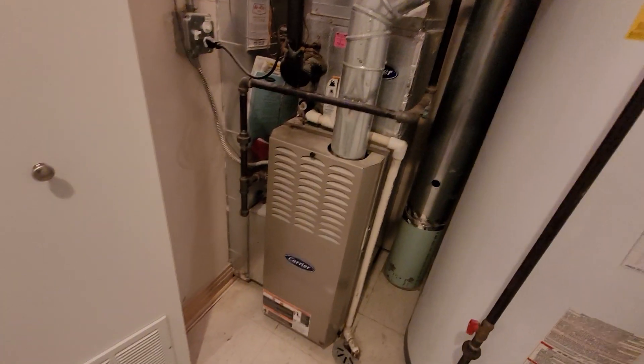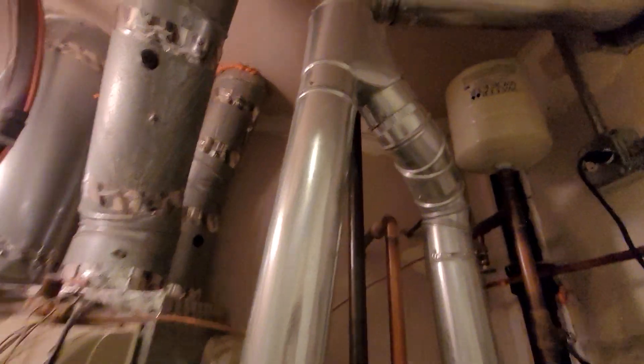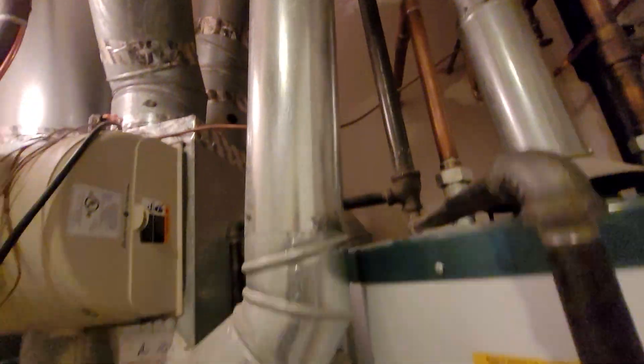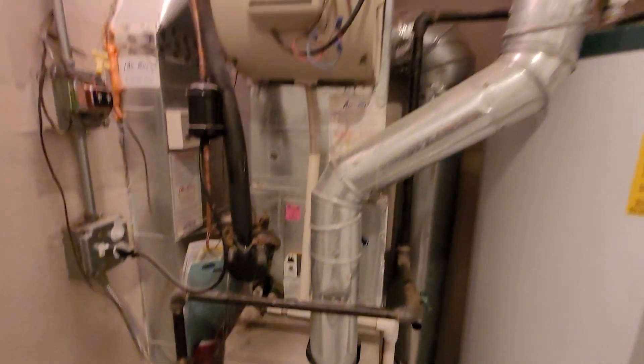Here in the twin downstairs system, right off the main entrance: 14-inch, 70,000 BTU single stage. 4-inch flue up to the collector. This one does not have near as much corrosion on it, but there is a tiny bit from the floor drain right beneath. 16x25x1 filter. We do want to delete the humidifier here.